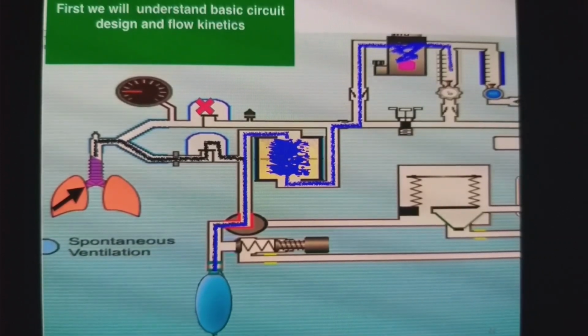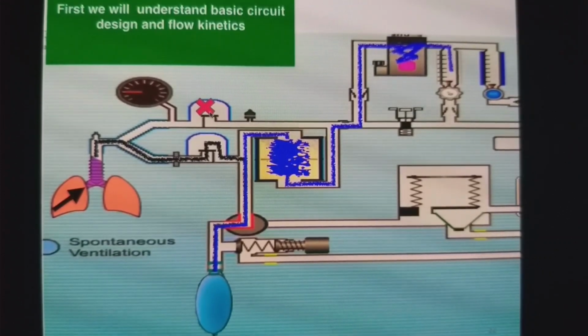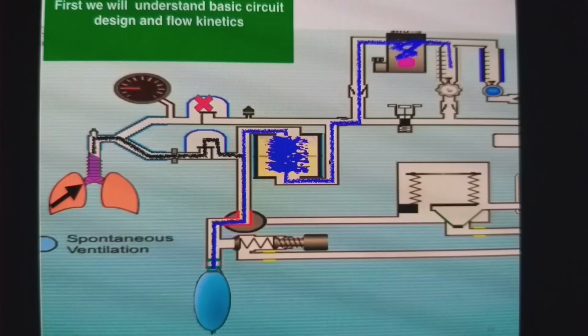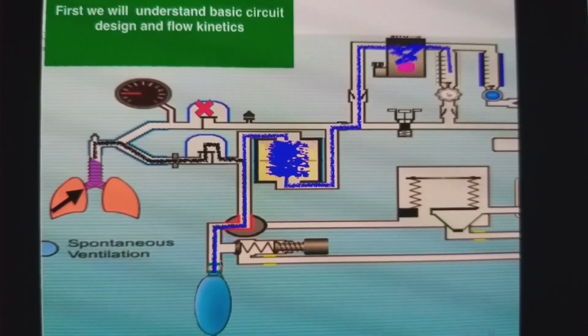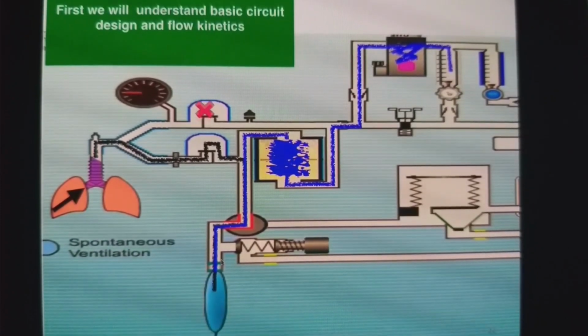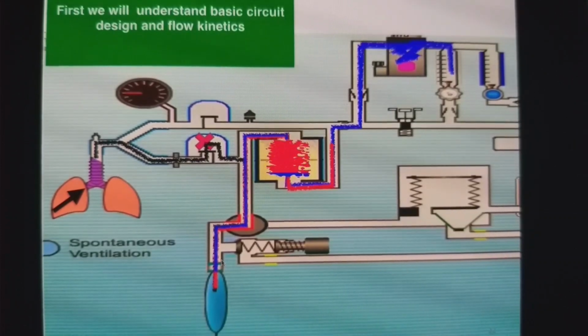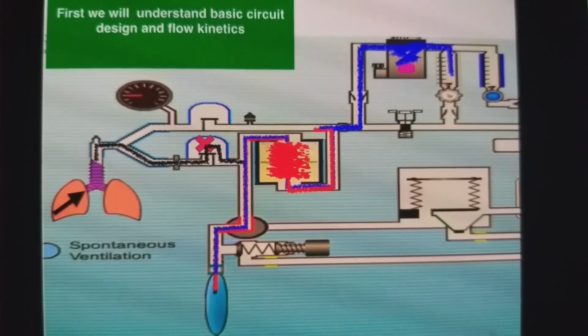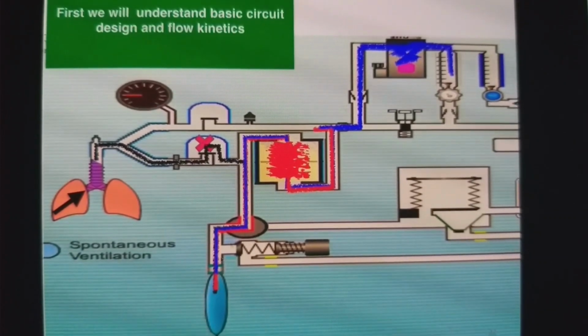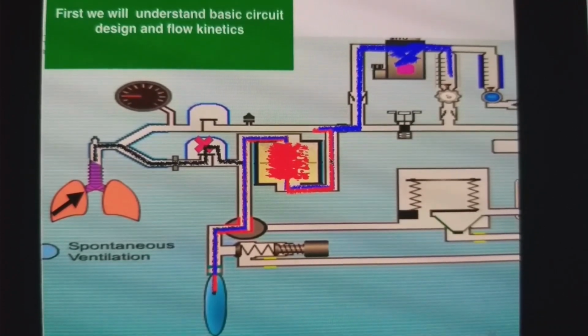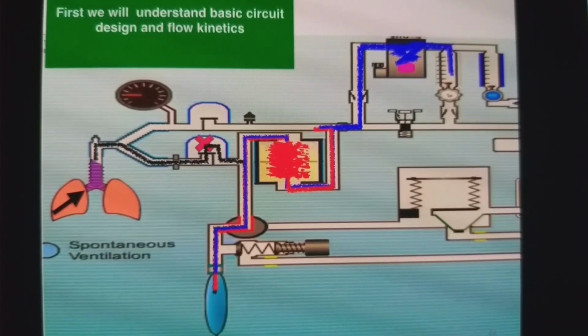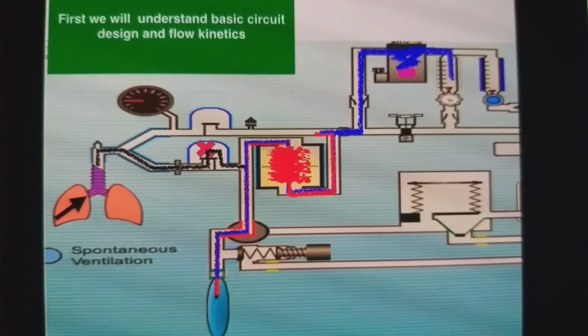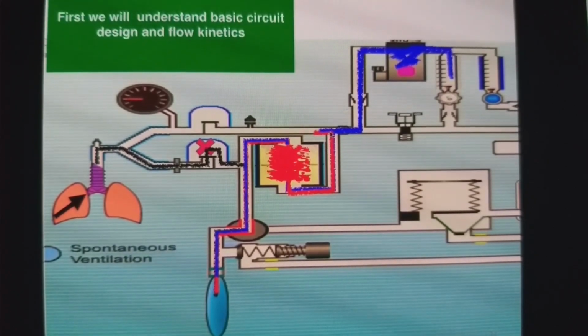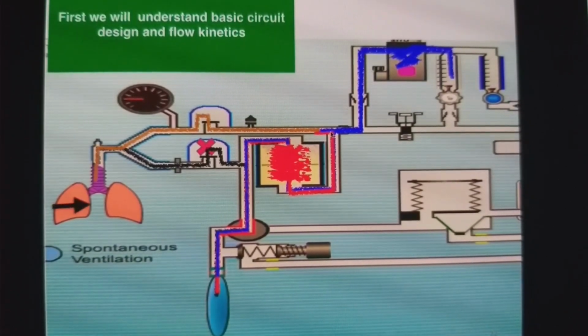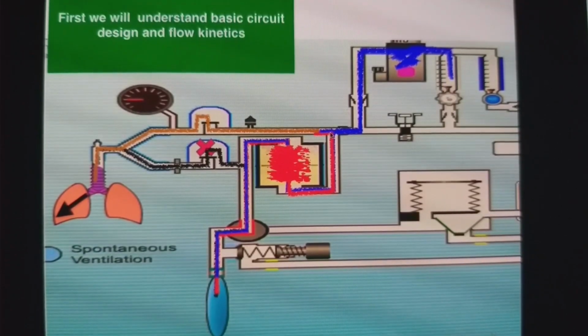At the same time, since the inspiratory valve is closed, fresh gas flow will also go to the reservoir. Now, when the patient starts taking a breath, that is inspiration, or when you decide to squeeze the bag, the gas in the reservoir bag will pass through the soda lime canister, and at the same time the fresh gas flow will join it, go to the inspiratory tubing through the inspiratory unidirectional valve, and go to the patient.